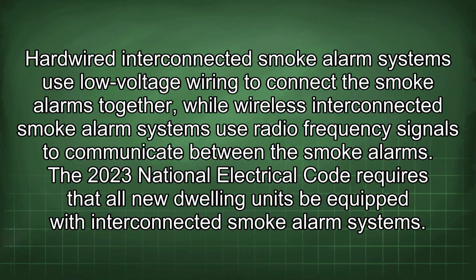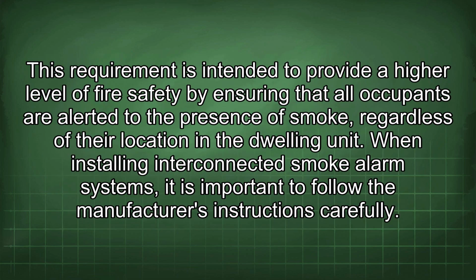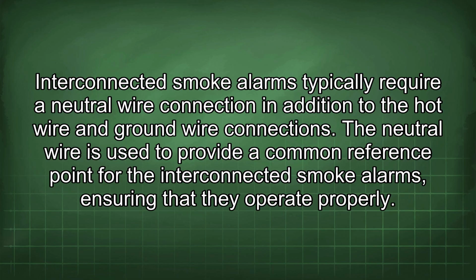The 2023 National Electrical Code requires that all new dwelling units be equipped with interconnected smoke alarm systems. This requirement is intended to provide a higher level of fire safety by ensuring that all occupants are alerted to the presence of smoke, regardless of their location in the dwelling unit. When installing interconnected smoke alarm systems, it is important to follow the manufacturer's instructions carefully. Interconnected smoke alarms typically require a neutral wire connection in addition to the hot wire and ground wire connections.